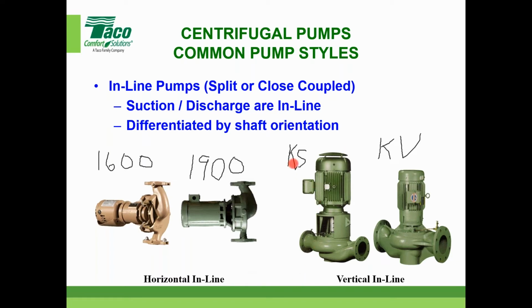With the KS pump, the split coupled, you can change the seal without moving the motor or affecting the piping. There's a whole video online that shows you how to do it, and it's in our instruction sheets as well that you have access to. So that's another reason you might specify these.